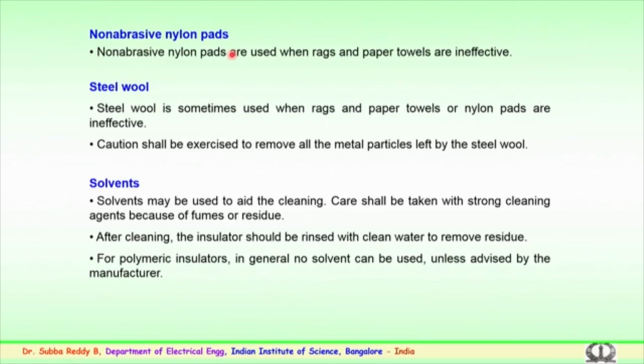The caution to be exercised is to see that all the metal particles left by the steel wool are removed. That is very important. These small particles from the steel wool, if deposited on the surface of the insulation, could lead to early breakdown of the surface. So care has to be taken once the cleaning is done. Any traces of metal particles left on the surface of the insulators have to be completely cleaned, and it must be checked after cleaning whether any metal traces are left over.